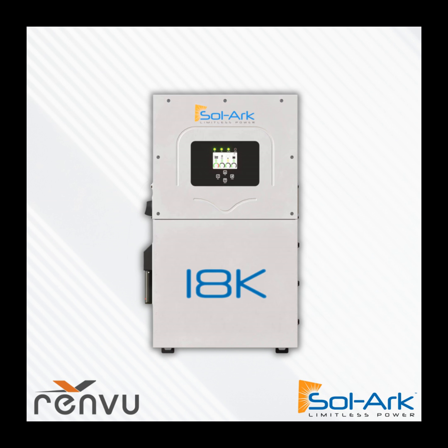We will talk about the Sol-Ark PCS listings. I see, Paul, you're saying one issue you're running into is not being able to backfeed Sol-Ark even on a 225 amp bus. I think you are misinformed on that, Paul, because if you go to the California Energy Commission list and look at their UL 1741 PCS listings, all of our inverters of merit, like the 12K and 15K, are PCS listed. So if the 18K is not on that list, I think it is, but if it's not on that list, it will be.